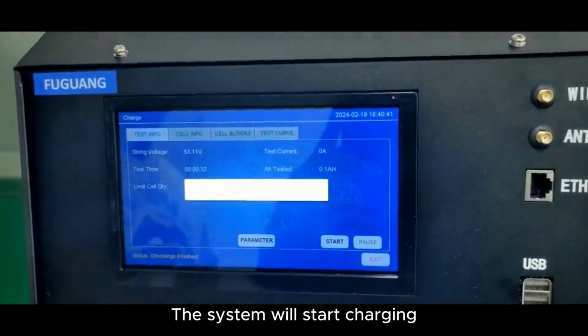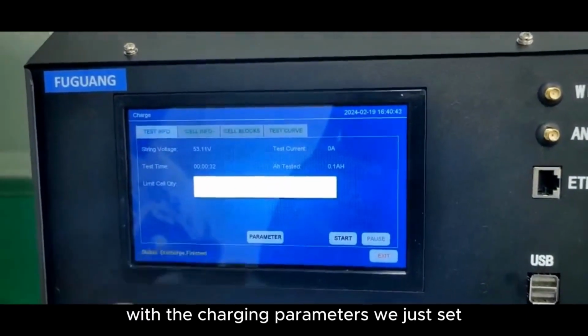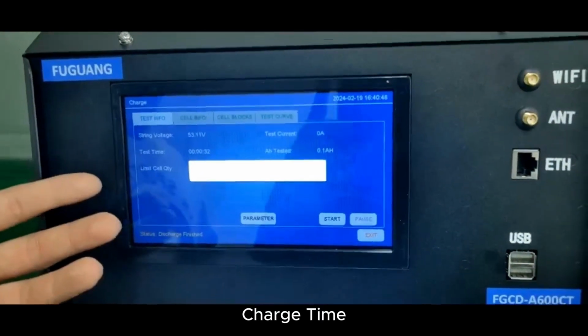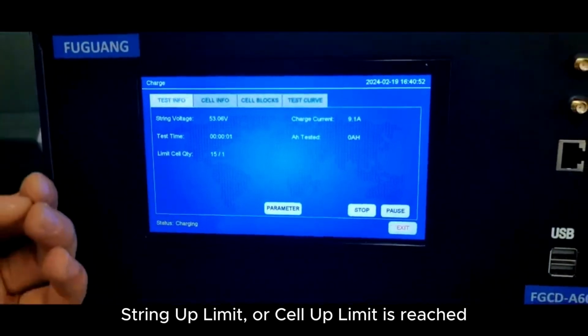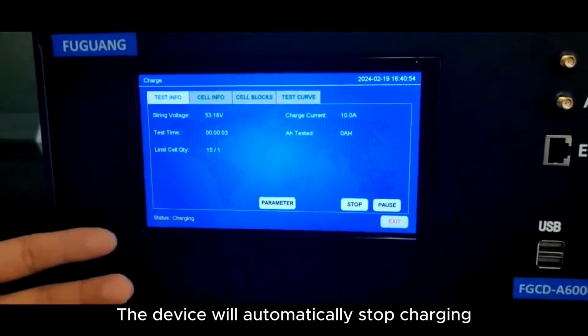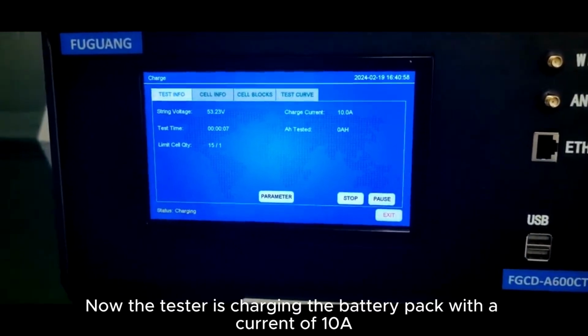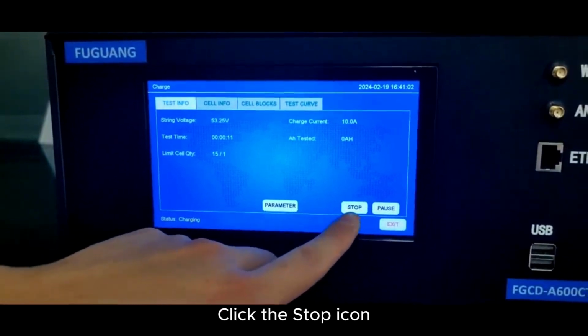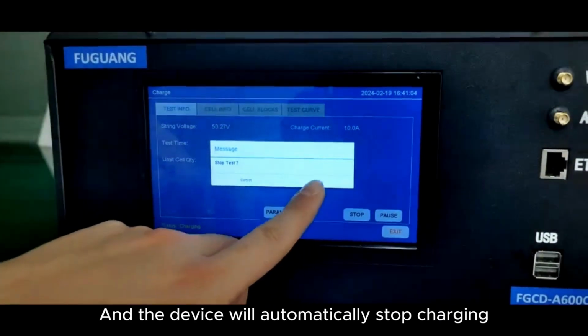Now we click Start on the charge test page. The system will start charging with the charging parameters we just set. When the end current, charge time, charge capacity, string up limit, or cell up limit is reached, the device will automatically stop charging. Now the tester is charging the battery pack with a current of 10 ampere. Click the stop icon, and the device will automatically stop charging.